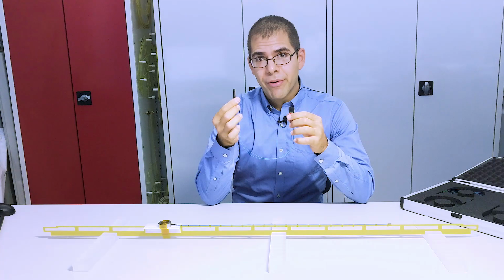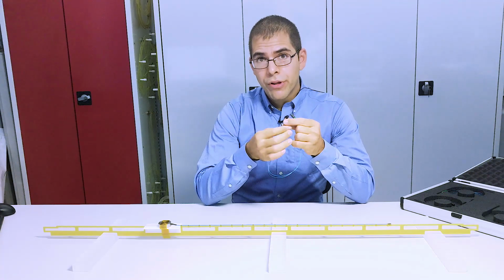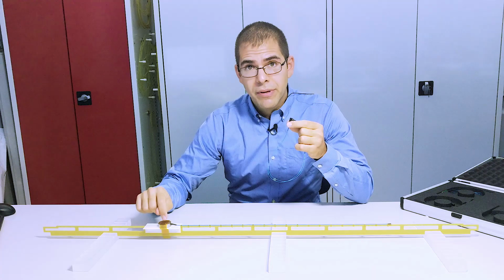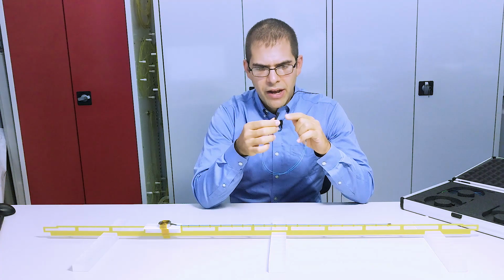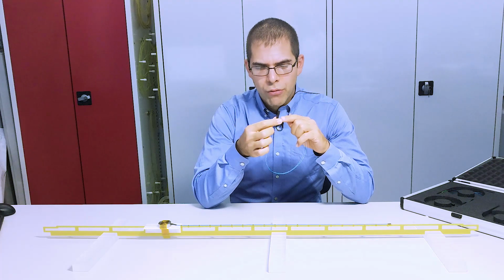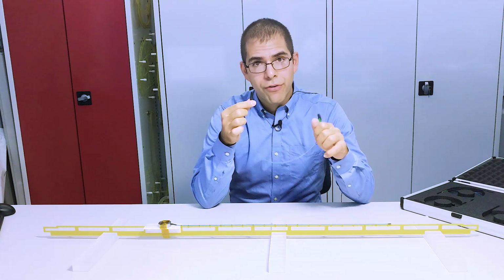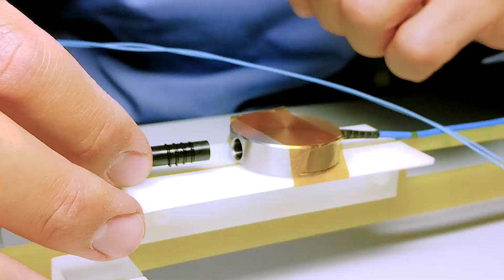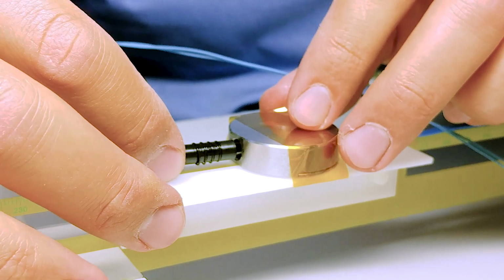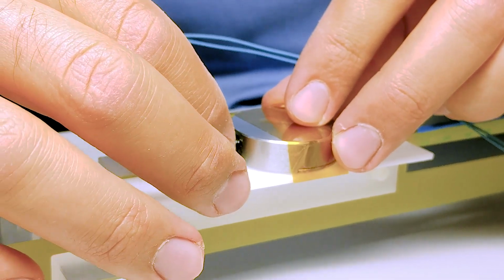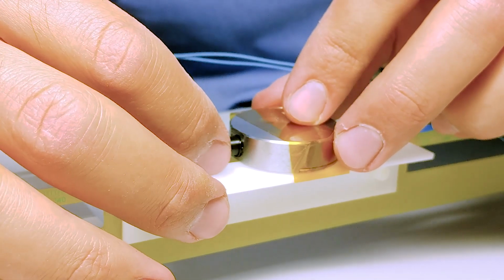This is the RF over fiber probe for medical applications. We'll use it to measure the induced voltage at the implant terminal. It has a tiny broadband transducer, which is connected by optical fiber over to the remote unit. Now I plug the probe into the validation device. It has these little silicone gaskets which help to waterproof the connection.